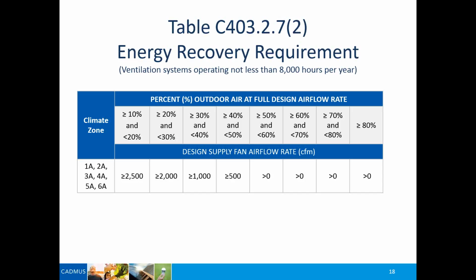Okay. So if I have a building that's operating, or a ventilation system operating, more than 8,000 hours per year, you can see now that even for 10 to 20% outside air, the very first column, if you have a fan system greater than or equal to 2,500 CFM, you're going to be required to have energy recovery ventilation. So in the hotter, humid climate zones, it actually makes sense, because not only are you cooling down the air, but you're also dehumidifying that air too. And so there's a significant amount of energy savings on here.